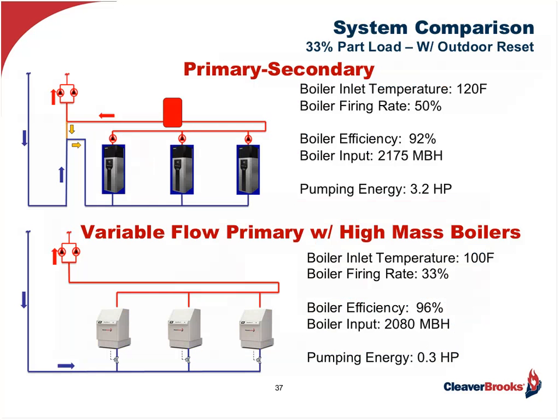The comparison, 120 versus 100, which look at the boiler efficiency, 96% for the high mass boilers, 92 for the boilers in the primary-secondary arrangement. And again, look at your pumping horsepower. We're using 3 horsepower more in pumping these boilers on the primary-secondary than on the variable flow primary.